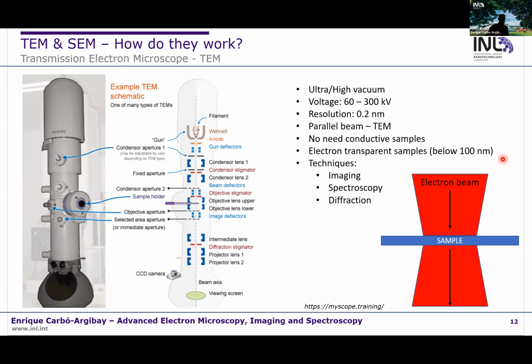In SEM, we just need conductive samples, and this is something that we can get easily with a layer of carbon, with a layer of some metal. However, in TEM, we need thin samples, and in case we have a bulk material, we have to do a previous sample prep to cut a piece of our sample and reduce the thickness to 100 nanometers or below. The advantage of the TEM is that the resolution is much better than in SEM, at least 10 times better. The voltage we use is a bit higher. In the SEM, we talk about 1 to 30 kV. Here we talk about voltages from 60 to 300 kV.